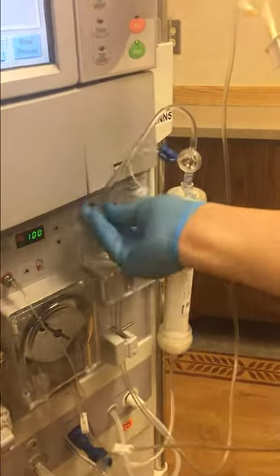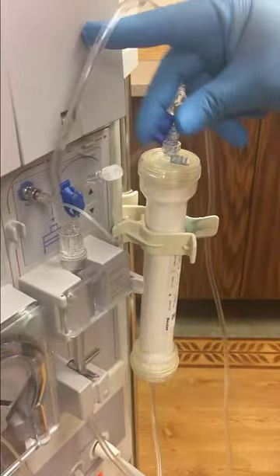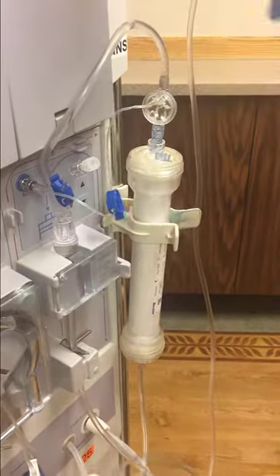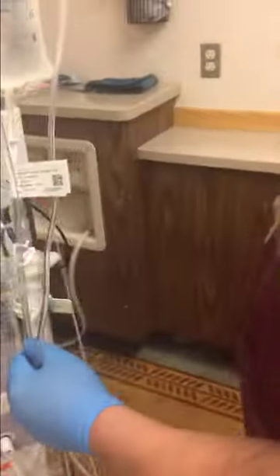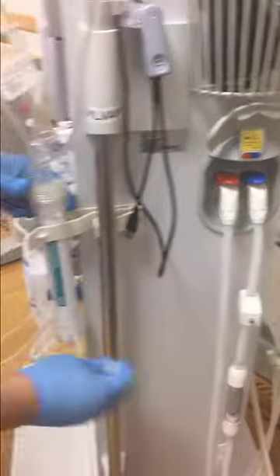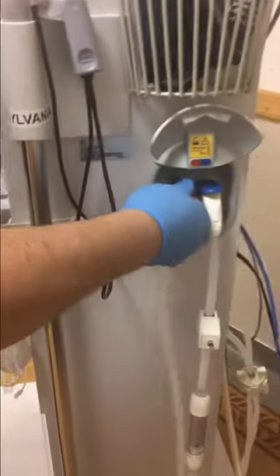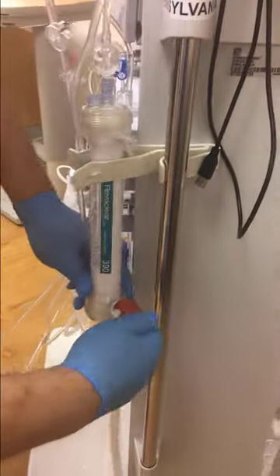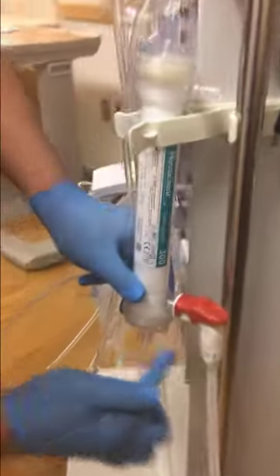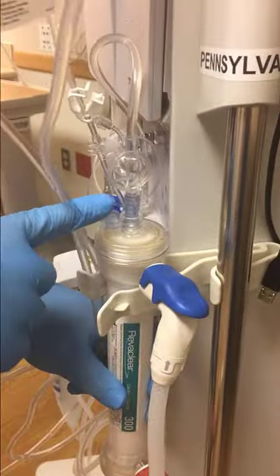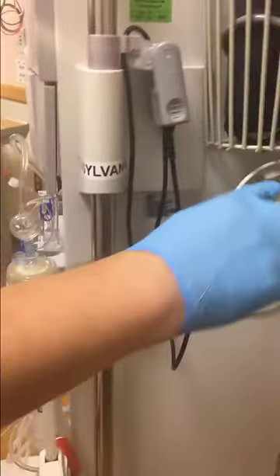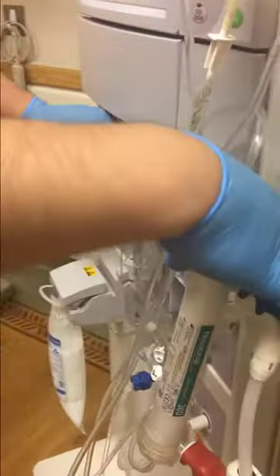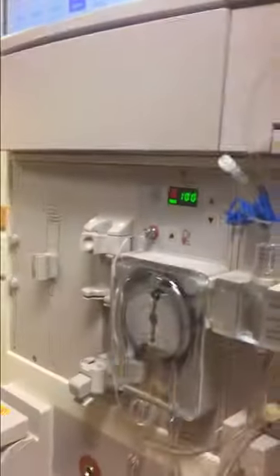Now we're ready to get our machine recirculating. So we're going to connect the venous transducer and unclamp it. And now we need to prime the dialyzer side of the tubing. The red Hansen goes on the red end of the dialyzer, and the blue Hansen goes on the blue end of the dialyzer. So blue to blue and red to red. And the blue end of the Hansen is the end that actually brings in fresh dialysate.